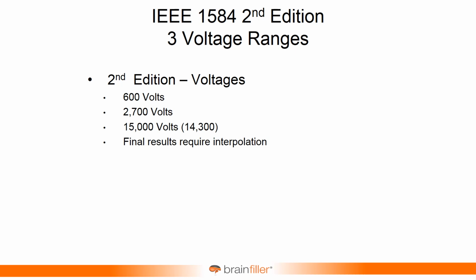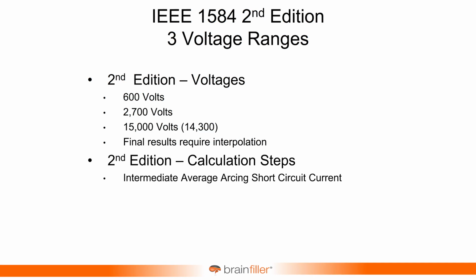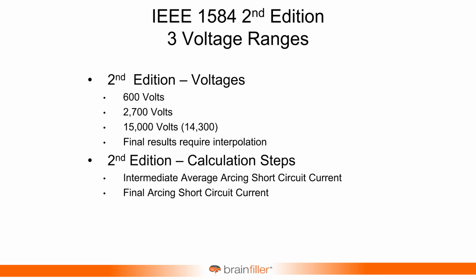And then what you do is you interpolate. Once you come up with your results, then there's an interpolation procedure that you go through to scale it into your actual voltage. So for example, if you're using 600 volt equations and your system is actually 480, your initial calculations will be based on 600 volts. But then you go back and interpolate and basically change it or adjust it to the 480 volt condition. The calculation steps, there's the intermediate average arcing short circuit current. And that's the initial calculation that I was talking about. Next, you calculate the final arcing short circuit current by interpolating for the actual system voltage. Then after that, there is what's referred to as the minimum arcing short circuit current.